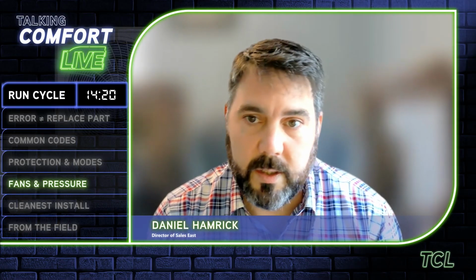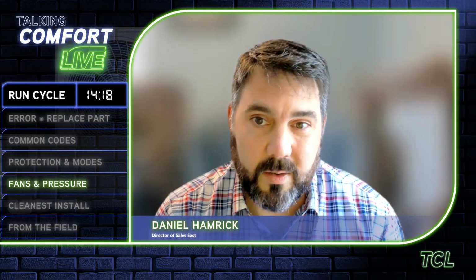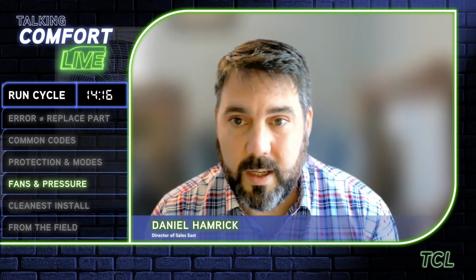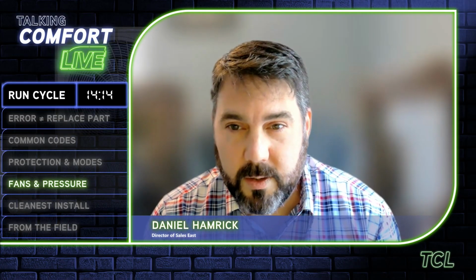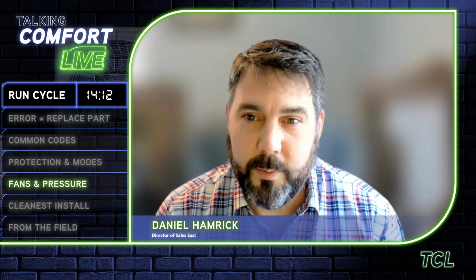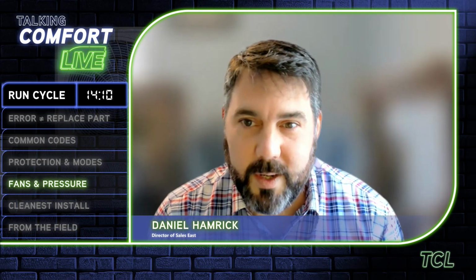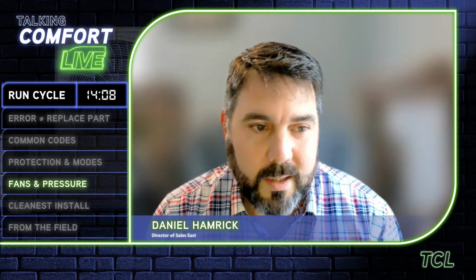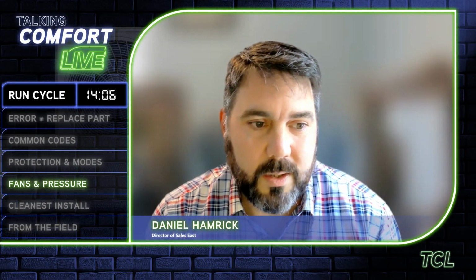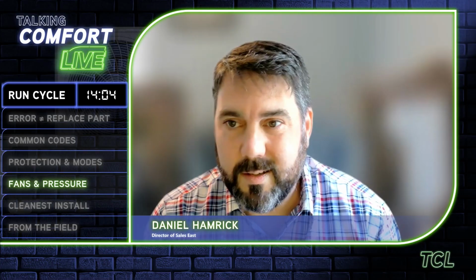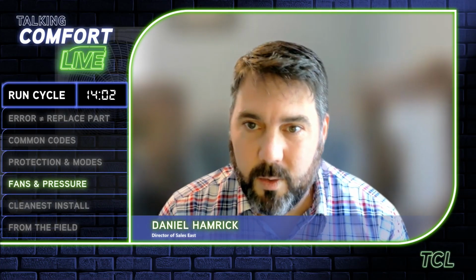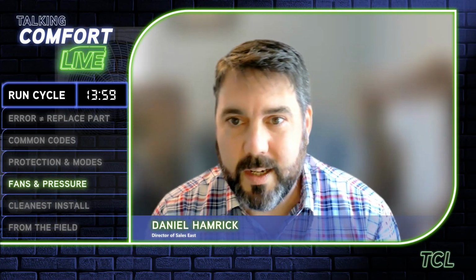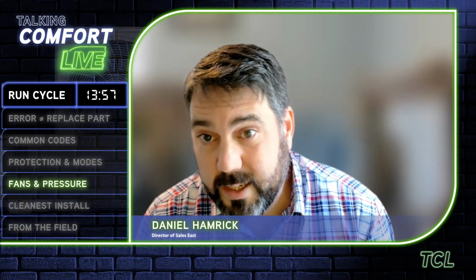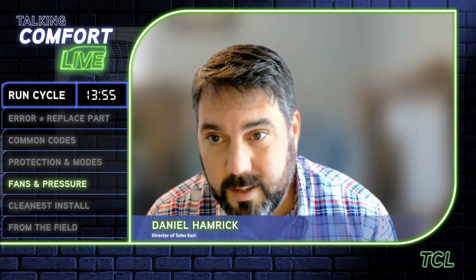The first time I learned this was between just a standard mini split and what we had, a U-Match back in the day. Yeah, a little bit different setup, it communicated a little differently, had a 2-wire separate communication. That H6 on one might mean indoor fan. Yep. That's right. H6 on the Flex, for instance, means an outdoor fan.